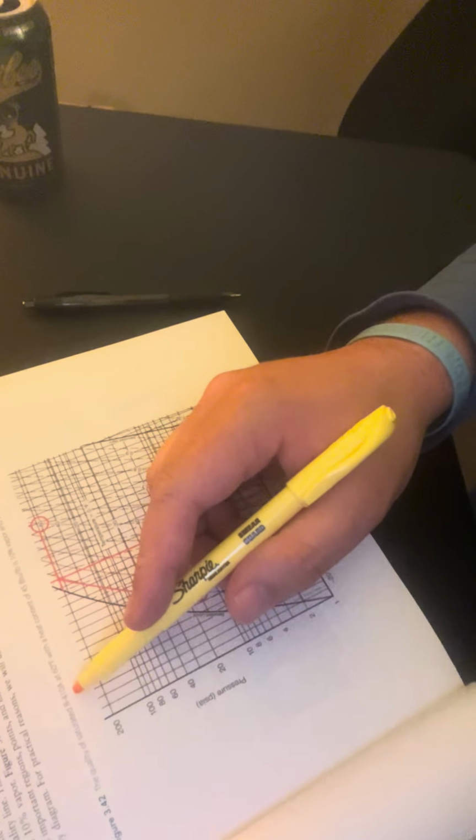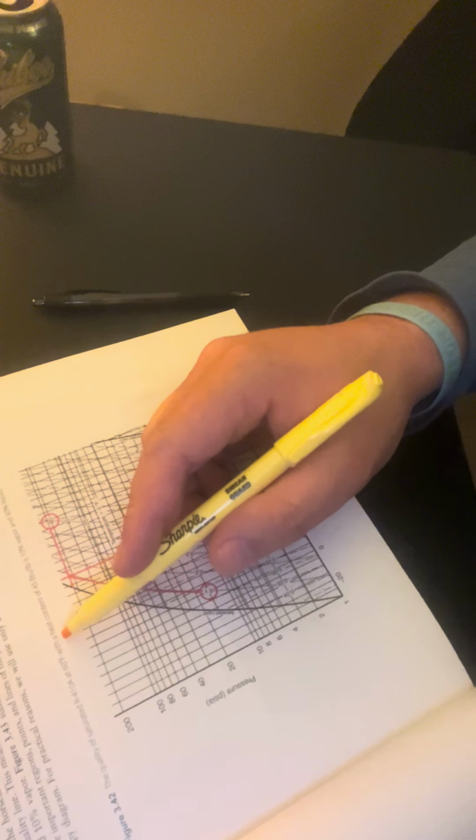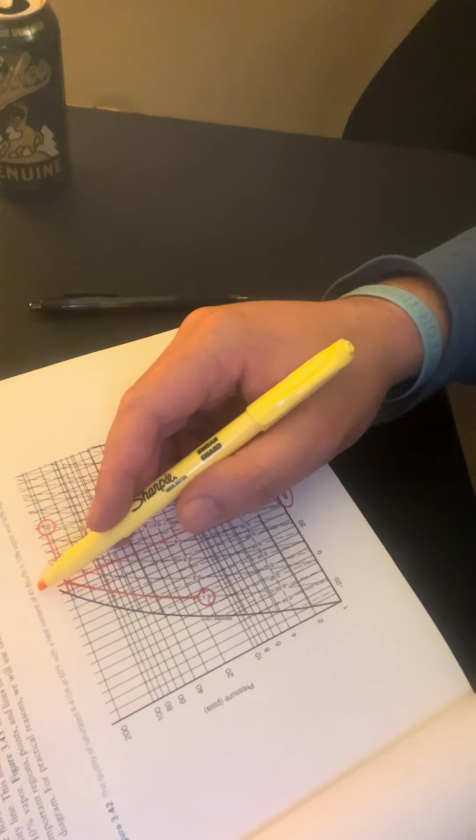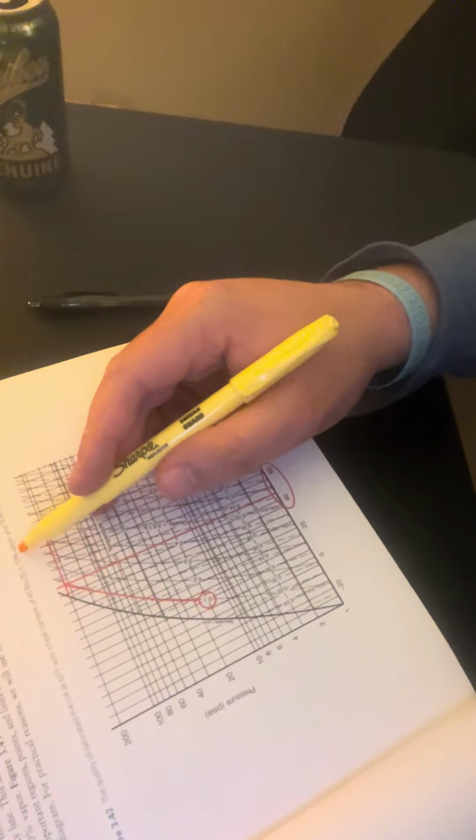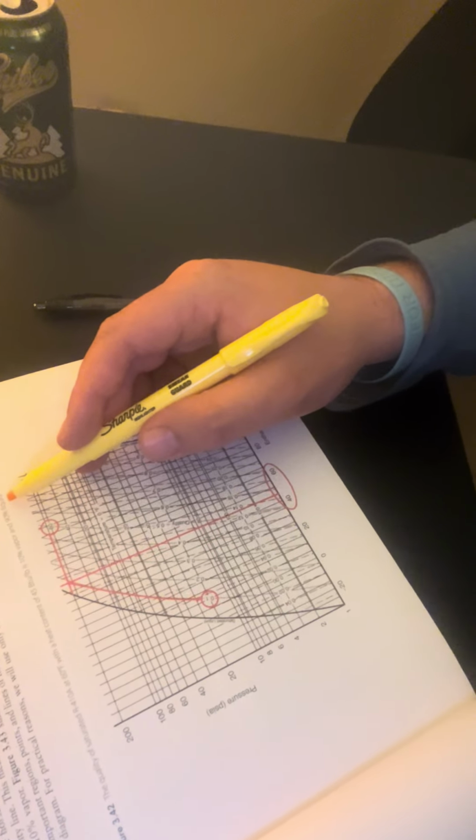The quality of saturated R410A at 60 degrees Fahrenheit with a heat content of 45 BTUs per pound is 10% vapor and 90% liquid. This point is underneath the horseshoe-shaped curve and lies on the 0.1 constant quality line. This means that the refrigerant is 90% liquid and 10% vapor. Figure 3.43, next page.